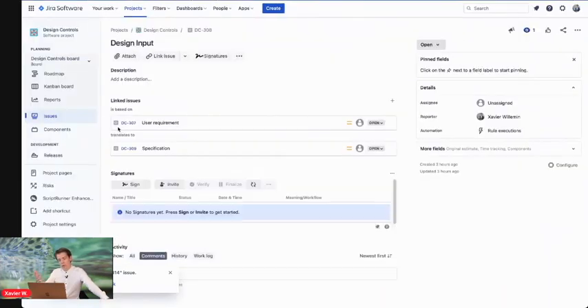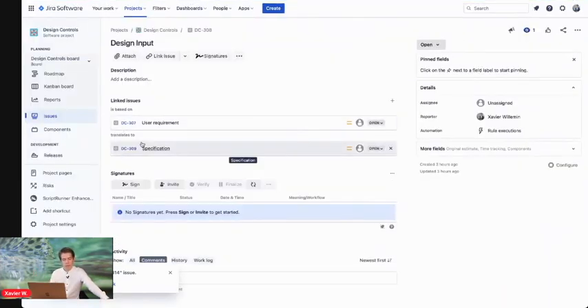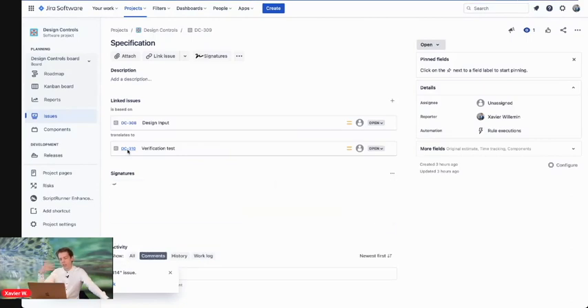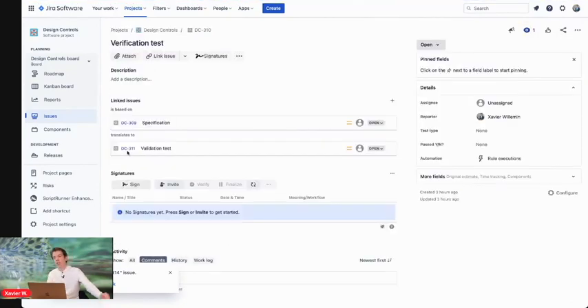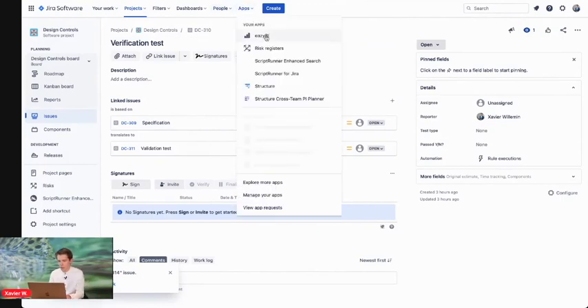You go now to design input, and you see it's linked to a specification, which itself is linked to a verification test, which itself is linked to a validation test. That's how you build your traceability. But then how do you actually see it? Where are the reports? The report is here, inside a structure which is a hierarchical view of all your design controls.